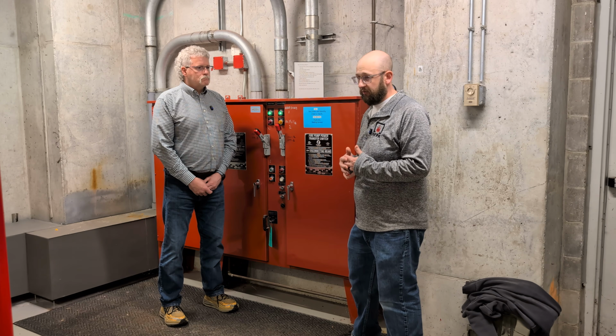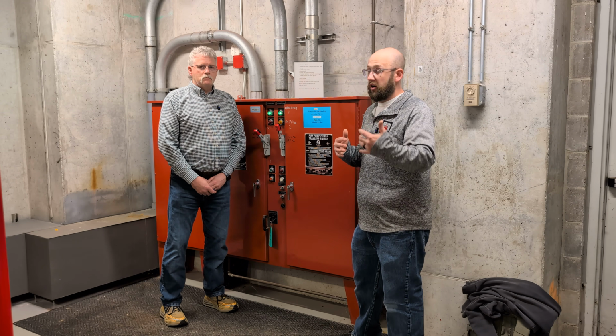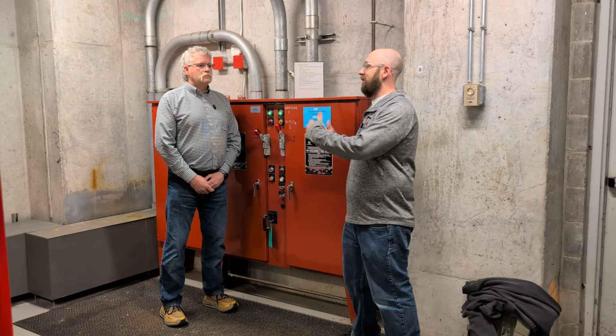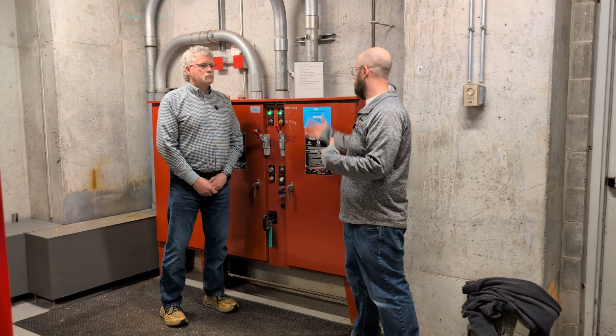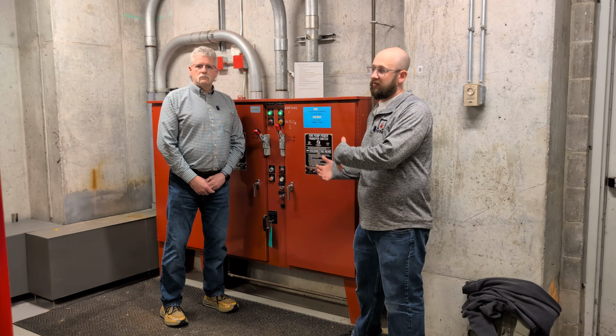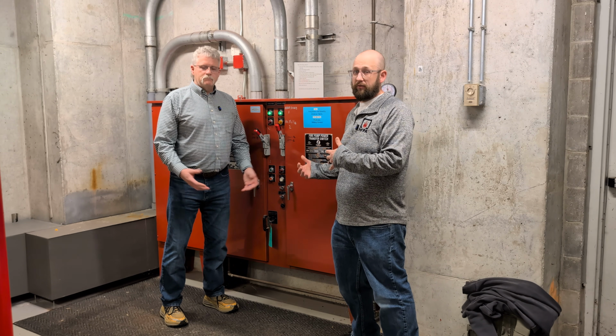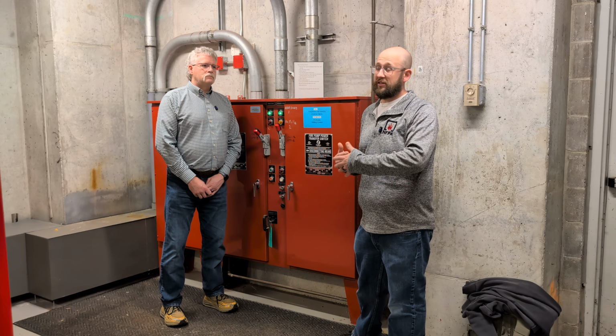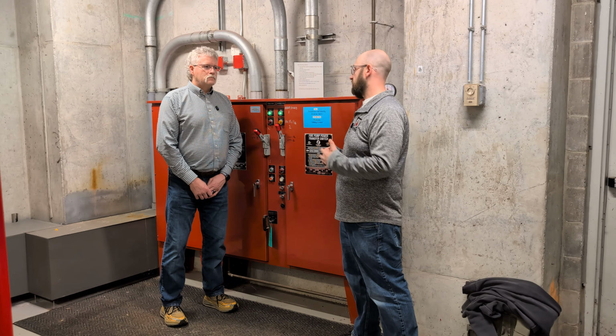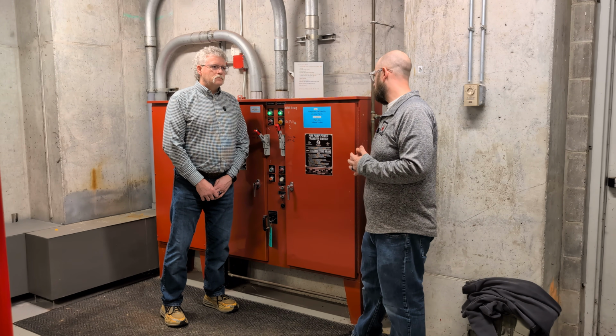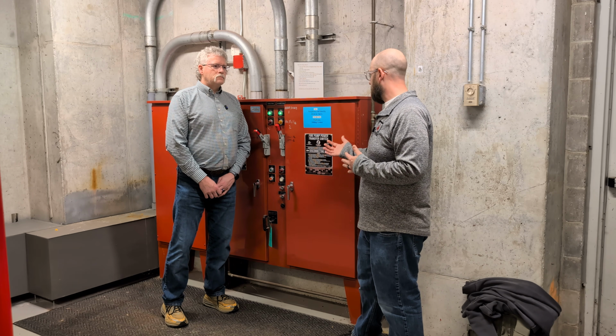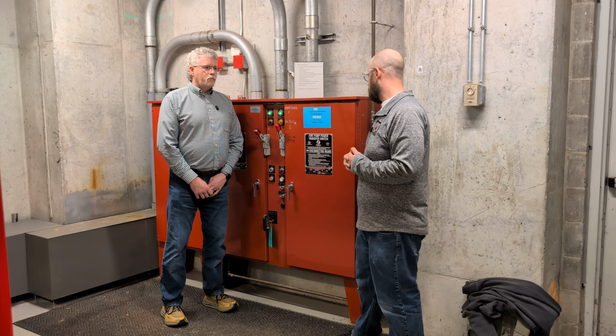Another thing to add for NFPA 20: if you are required to have an alternate source of power, it doesn't mean you have to put in a generator and a transfer switch. You could just do a second fire pump. You could do a diesel-driven fire pump and have two pumps instead of an electric pump with a backup. So that's one example of how you could get away without it, but that's a good example of how we have that transfer switch. I appreciate, Dean, you giving your insight on that as well.